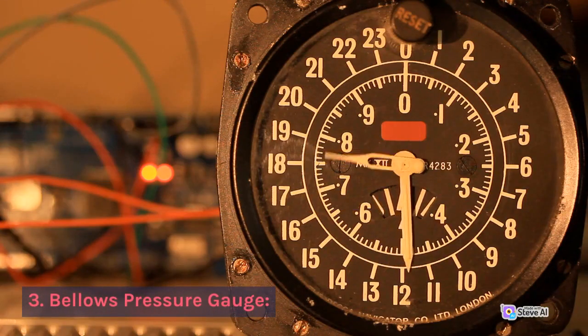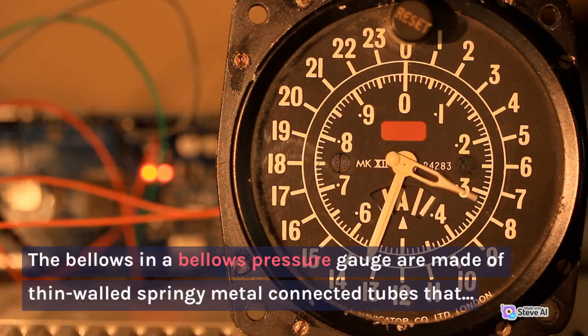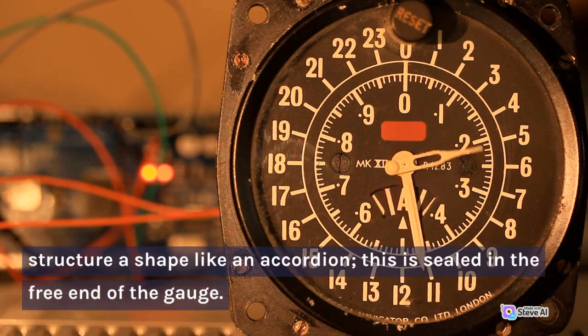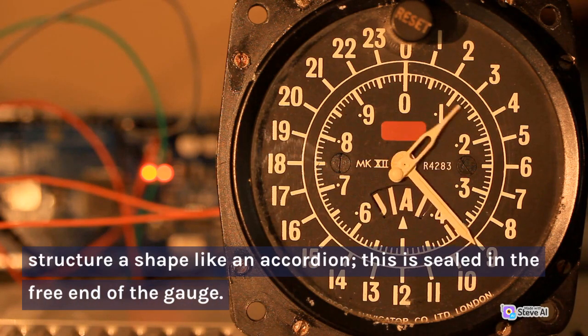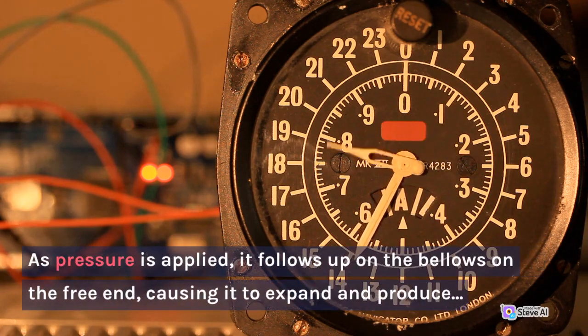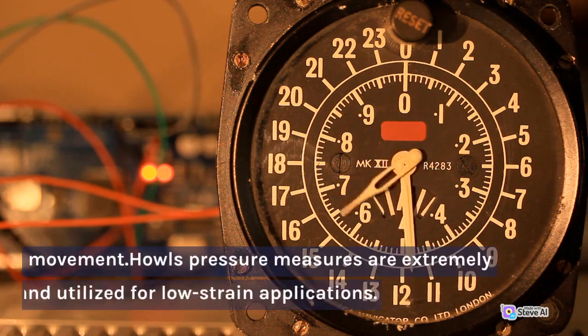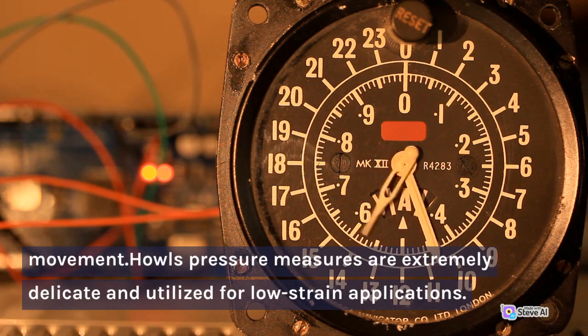3. Bellows pressure gauge. The bellows in a bellows pressure gauge are made of thin-walled springy metal connected tubes that structure a shape like an accordion. This is sealed in the free end of the gauge. As pressure is applied, it follows up on the bellows on the free end, causing it to expand and produce movement. Bellows pressure gauges are extremely delicate and utilized for low-pressure applications.